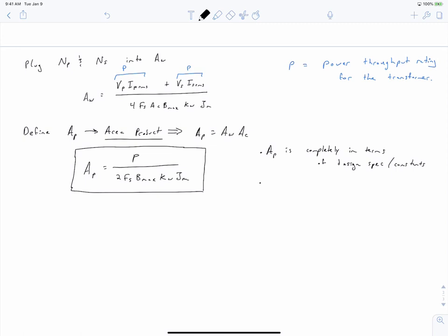You could have a very small window and a very large core, or a very small core and a very large window, and to a first-order approximation it doesn't matter. In all actuality, you need a well-dimensioned system to avoid too much leakage flux or manufacturing issues. But core manufacturers go to great lengths to optimize their core dimensions within this area product concept, so if you pick one of their cores with the correct area product, they've put thought into dimensioning their window versus core area for a reasonable design.